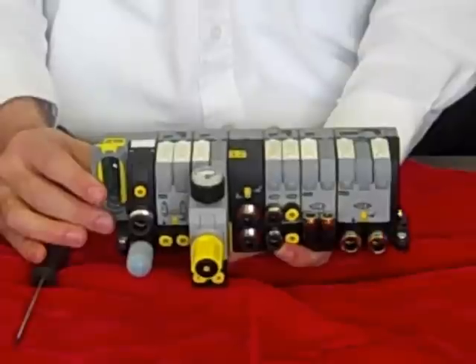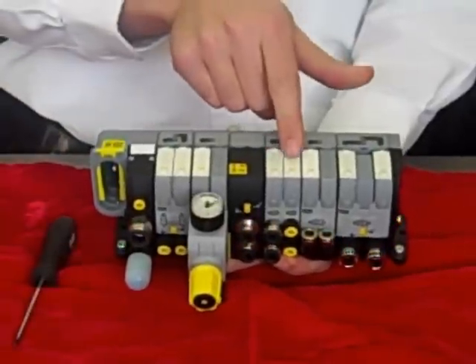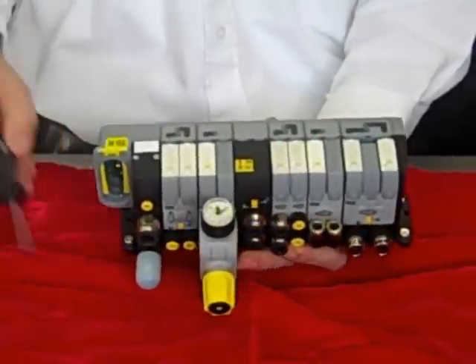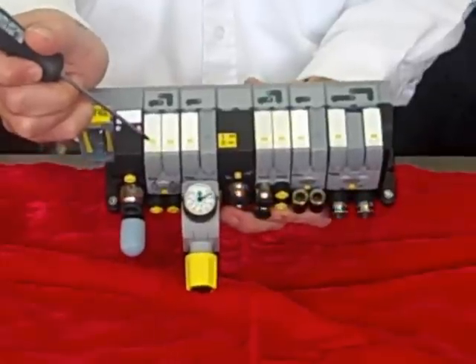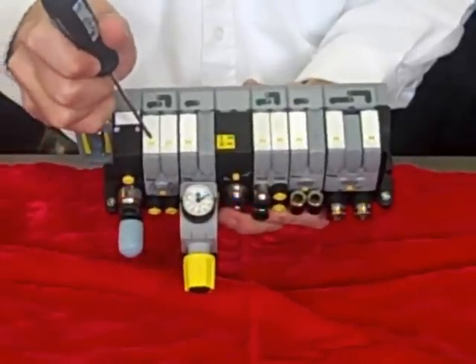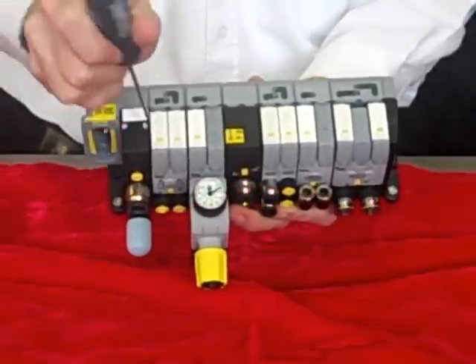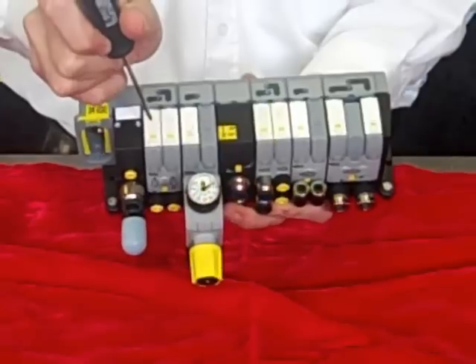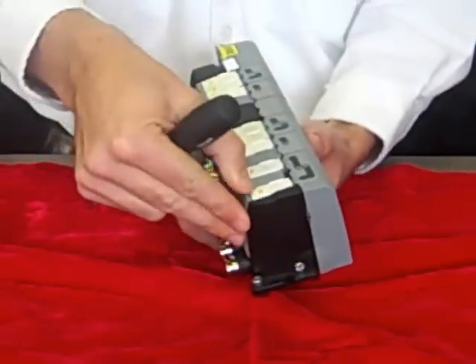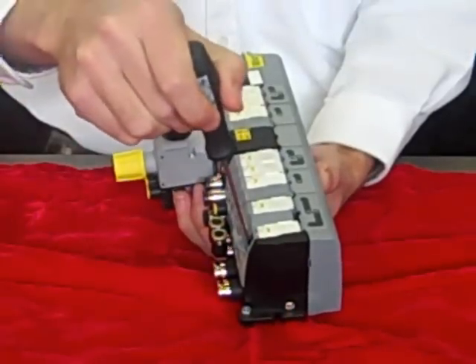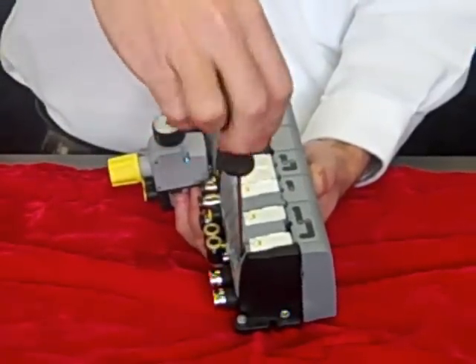The solenoids for the valves are conveniently located on the top of each valve. The yellow button is the manual override, which can either be pushed in for a non-locking override or pushed and twisted for a locking override. Also, this allows easy replacement of solenoids, again, simply with one screw.